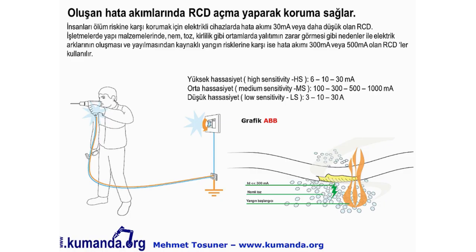İnsanları ölüm riskine karşı korumak için hata akımı 30 mA veya daha düşük olan RCD'ler kullanılır. Yangın risklerine karşı ise 300 mA veya 500 mA'lık RCD'ler kullanılır. Hassasiyet sınıflarına göre: yüksek hassasiyet için 6, 10, 30 mA; orta hassasiyet için 100, 300, 500, 1000 mA; düşük hassasiyet için 3, 10, 30 A'lık RCD'ler ayrılabilir.